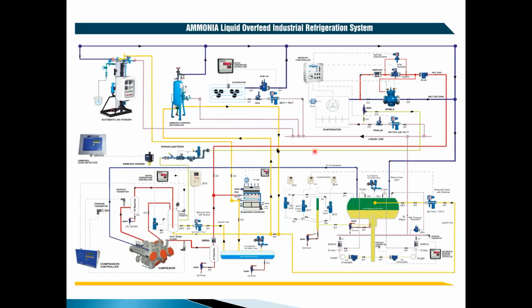releasing the condensed return. So what happens in hot gas, normally liquid will come in. These pumps are normally designed for higher flow capacity so as to make sure that all the evaporators are fully flooded. Typically, depending on the plant requirement, the circulation ratio can be 1:2, 1:3, 1:4, or as high as 1:6. It means that whatever liquid is fed here, one part of the liquid will evaporate, that is the required liquid, and the rest, like it's 1:4.